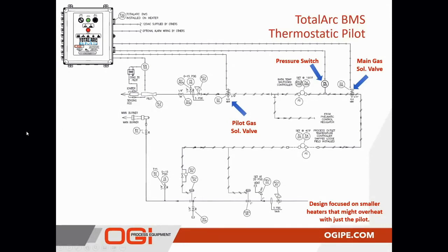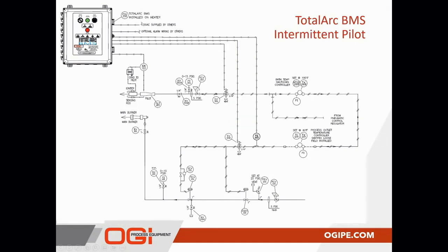For the TotalArc BMS intermittent pilot in a pneumatic configuration, the pilot will cycle on and off with the main burner when the heater safeties are okay and a call for heat is present. Again, in this case, we're relocating that BMS control pressure switch, and it's located after the pneumatic safeties and the pneumatic temperature controls. When the safeties are proven okay and a call for heat is received, the BMS will energize the pilot solenoid valve and light the pilot. After the pilot is proven, the main solenoid will be energized and the main burner will be lit.